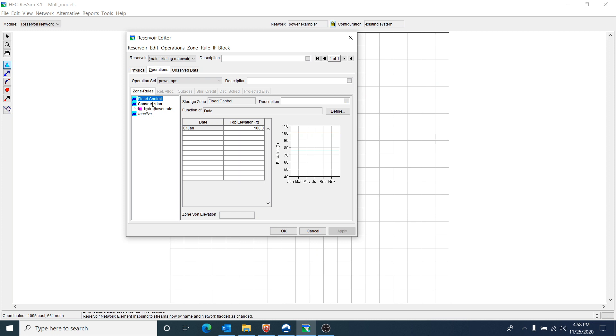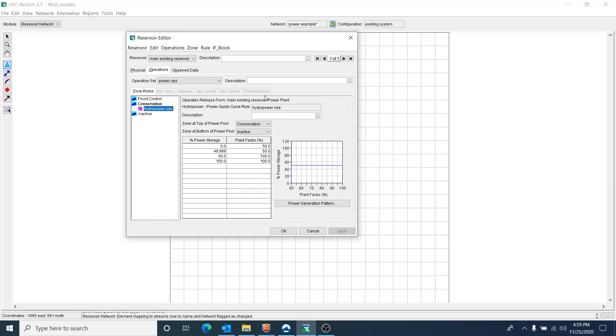I wanted to look at the operations. I have an operations set called Power Ops with just one rule — a hydropower rule in the conservation zone. I use the standard zones: flood control, conservation, and inactive. The top of the power pool is the top of conservation, and the bottom is the top of inactive. If I'm in the bottom half of this power pool, I'll have a plant factor of 50%. If I'm in the top half, 50 to 100%, I'll have a 100% plant factor. It's probably not realistic, but it helps to interpret results when learning about power in ResSim.